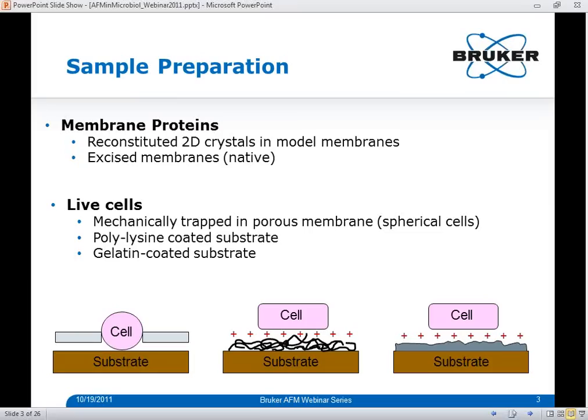The most important requirement in sample preparation for AFM studies, especially when conducted in fluid, is that the specimen be sufficiently immobilized on a suitable substrate so that it's not distorted or dislodged by the lateral motion of the scanning tip. For excised native membranes or reconstituted model membranes, this is typically achieved by simple physical adsorption to a flat substrate like mica, glass, or silicon. While some researchers conduct AFM studies in air by rinsing and drying cells, the cell surface undergoes changes during the drying process that can introduce structural artifacts, and therefore must be considered in interpreting the results.